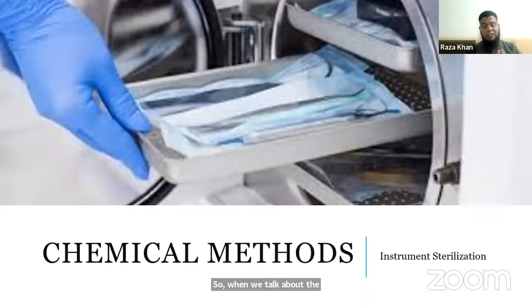So, ultrasonic cleaning is a cleaning method, not a proper sterilization method. When we talk about the chemical method of instrument sterilization, it usually involves two types: chemical sterilization with the help of machines and chemical sterilization without the help of a machine. The common method which requires a machine is ethylene oxide.